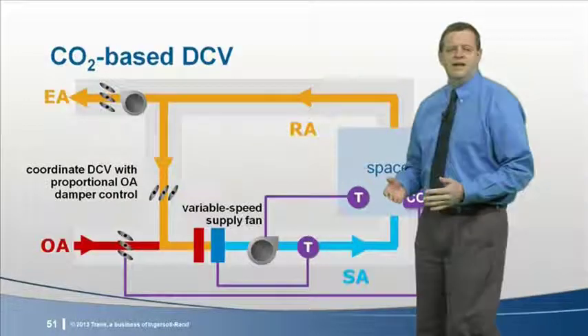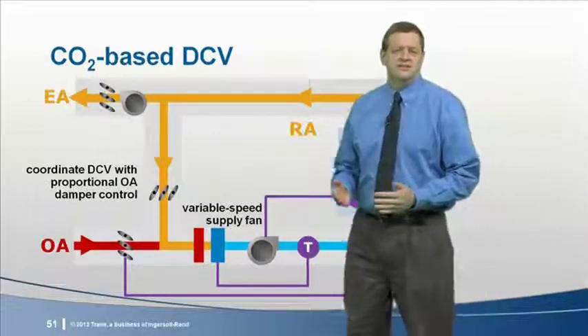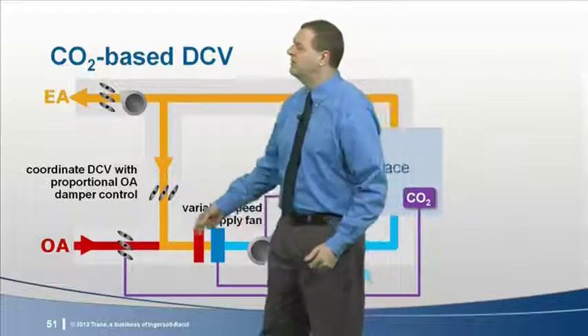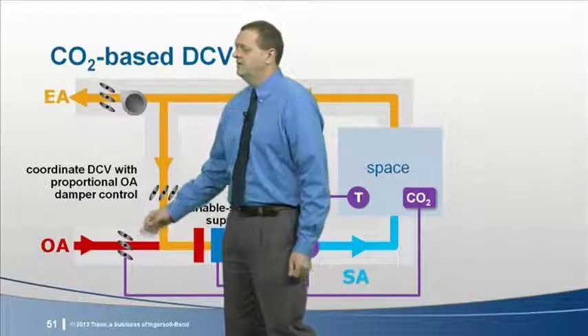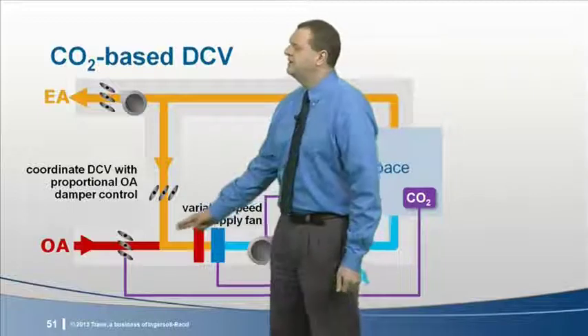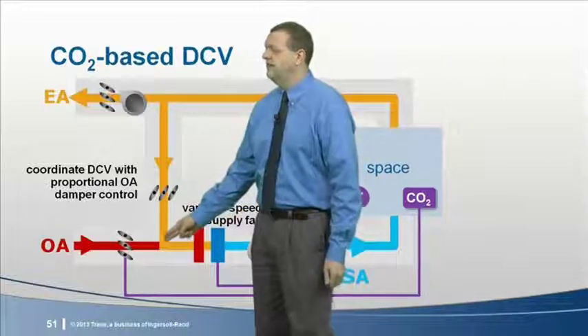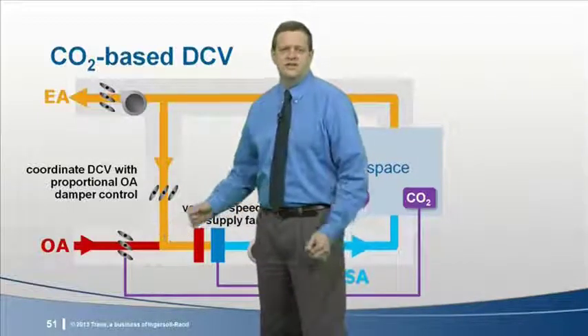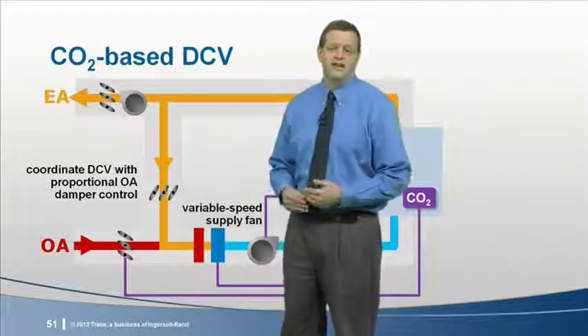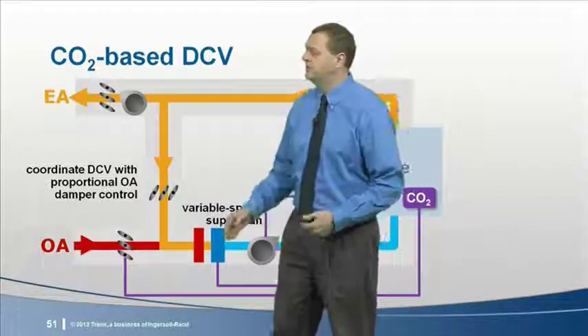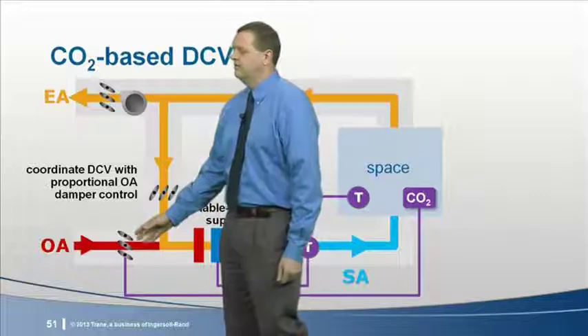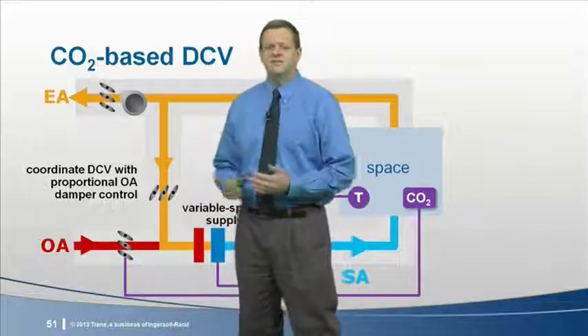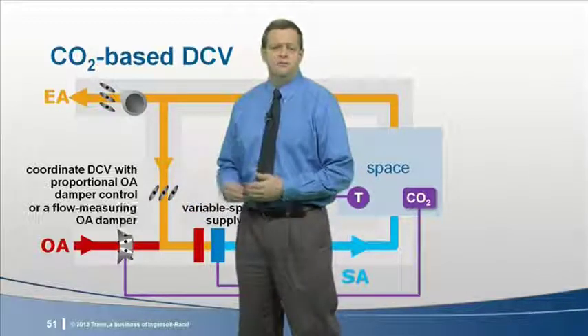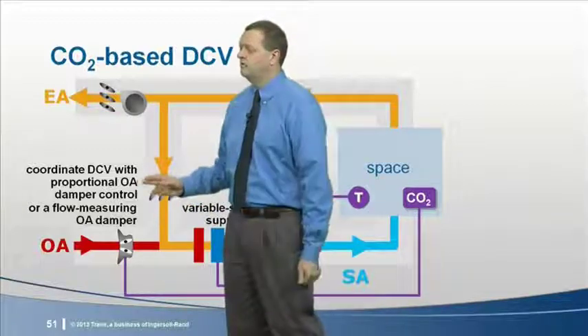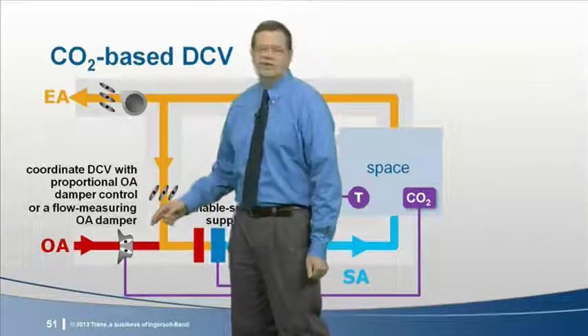So when implementing demand control ventilation, Standard 62 does not allow you to go below a certain CFM. The challenge is this: because this mixing box pressure varies as supply airflow changes, you need to make some provision to prevent outdoor airflow from dropping below this minimum CFM threshold. So even when using a CO2 sensor for demand control, it must be combined with either proportional control or a flow measuring outdoor air damper.